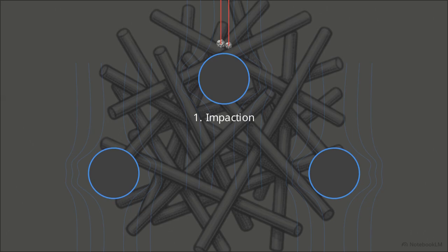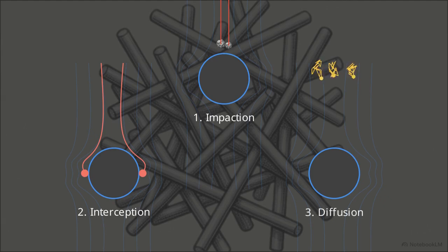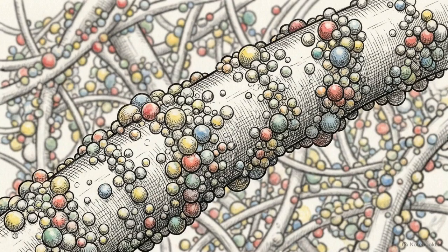First, impaction. Large particles possess too much energy to navigate twisting currents, slamming directly into fibers. Second, interception. Mid-sized particles follow curved airflows but graze fiber sides, snagging permanently. But particles under 0.1 microns stop obeying aerodynamic rules entirely. Lacking significant mass, they suffer constant random molecular bombardment, known as Brownian motion. This erratic zigzag path dramatically increases their odds of eventually striking a fiber and locking in place. HEPA filtration functions as an engineered probability matrix, where even the most elusive particles eventually collide with a fiber surface.